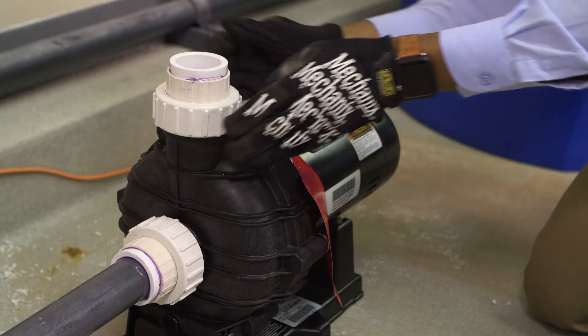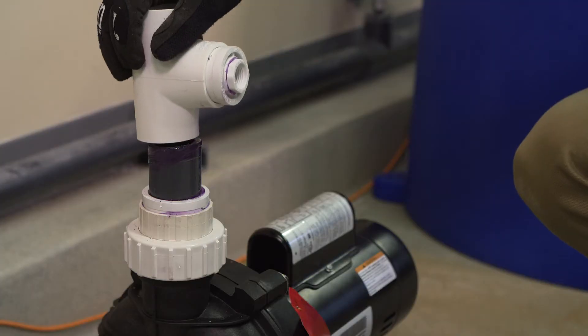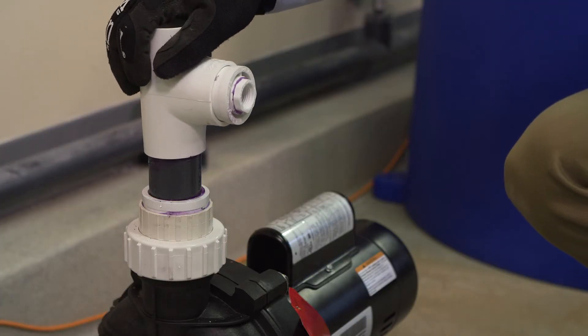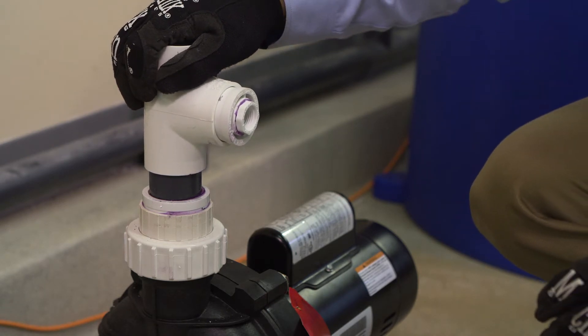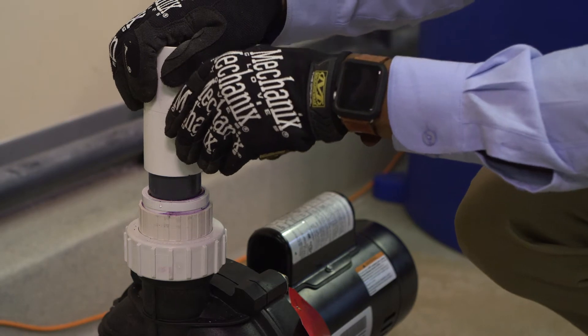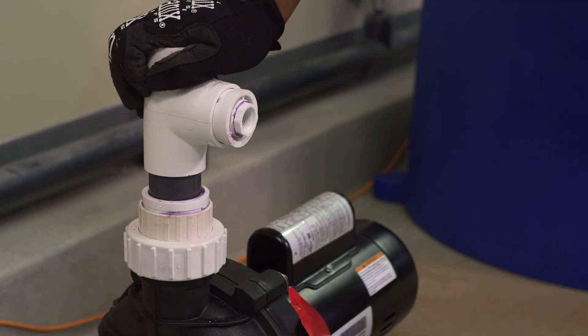Piping the discharge side of the pump will involve installing a Venturi and reducing T. Place and glue the 1.5-inch by 1.5-inch reducing T on the 1.5-inch cut nipple on the discharge side of the pump. This reducing T will have a 1.5-inch male tubing fitting screwed into it that will provide the inlet water to the feeder.